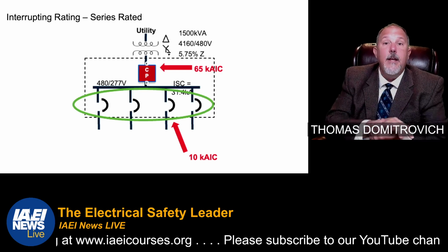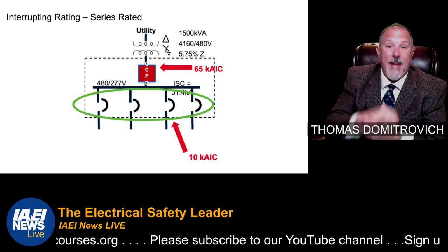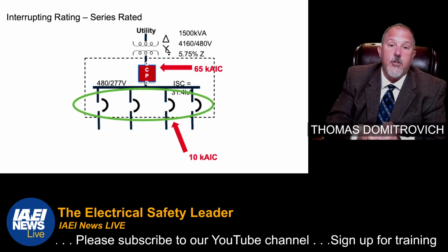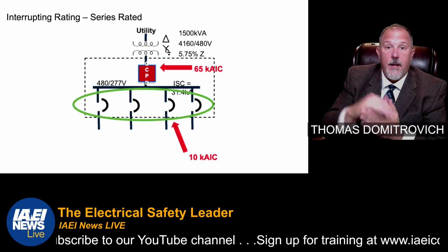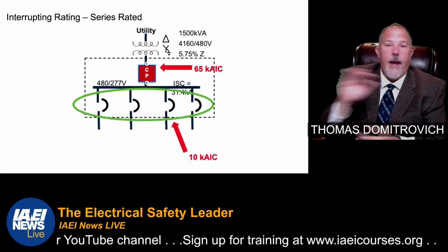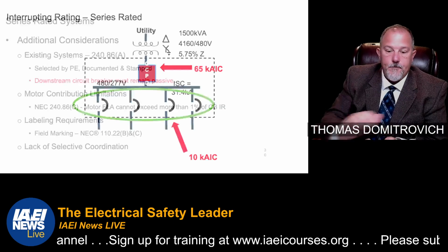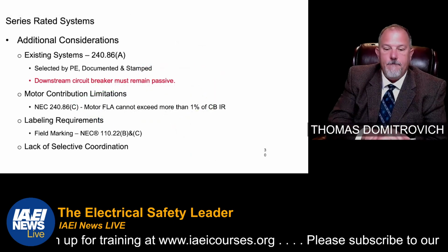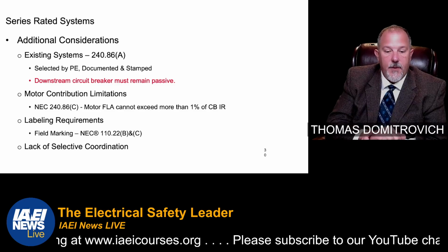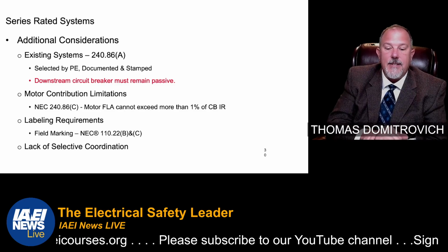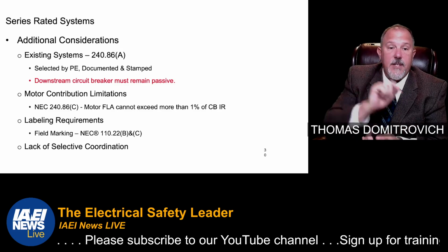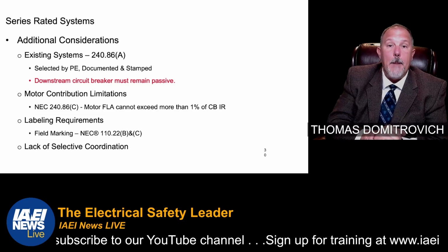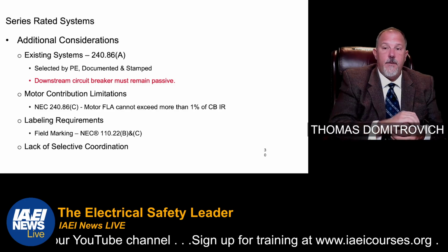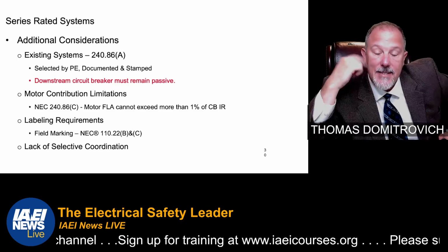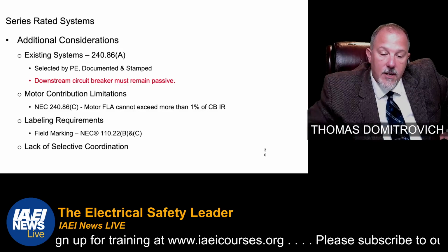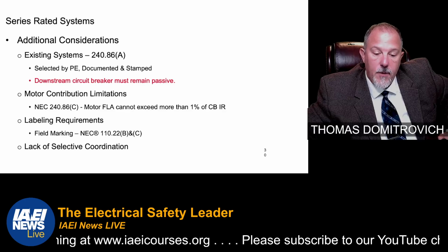I can never have a fuse downstream, protected by a circuit breaker or protected by another fuse. I can only use a circuit breaker downstream because the circuit breaker will have a lower interrupting rating. If I have a 10K interrupting rating fuse downstream, I cannot put anything upstream to increase the short circuit current rating of that equipment and protect it. And two fuses ain't gonna happen. Okay, so 240.86(A) tells you how to deal with existing systems. 240.86(C) deals with the motor contribution. I would say this one is missed by many engineers out in the field. They forget about 240.86(C), motor full load amps. I'll talk about why. And then you have to have it properly field marked.